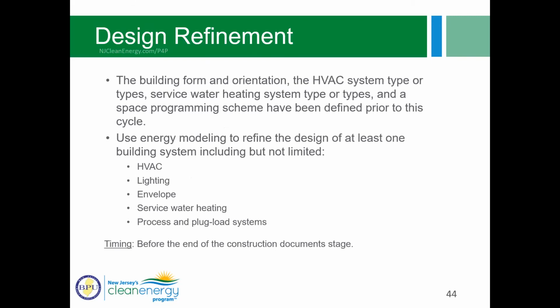All right, the next stage is design refinement. So the building form and orientation, and the HVAC system type, and service water heating system types, and the space types have been set at previous cycles. And now you use energy modeling to refine the design. And per Standard 209, you do this for at least one building system listed here, and it's not limited to those, but you want to focus on at least one building system during this modeling cycle. And you want to do this before the end of the construction document stage. So let's go over an example to illustrate what kind of thing you would do at this stage.